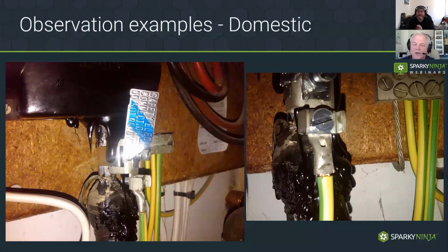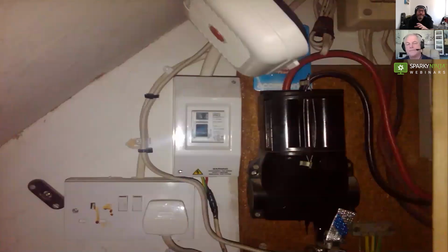Okay, same installation here. We can see an RCD unit to the left, and the cable at the bottom - we can see red, which means there's no fault protection for that conductor, no sheathing around there. So we've lost basic and fault protection. This has to be considered a C2, surely. Yeah, at least - there's one action. There's no fault protection, is there?